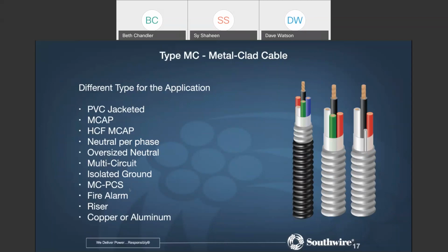For riser, the riser MC is a great product for, let's say you're putting in a high rise, and if you were installing standard MC cable, or if you were installing pipe and wire type of installations, single conductors in conduit, there is an NEC limitation on the vertical height that you can install those without putting in some kind of conductor support to ensure that the conductors do not fall out of the conduit or fall through the armor on an MC cable.